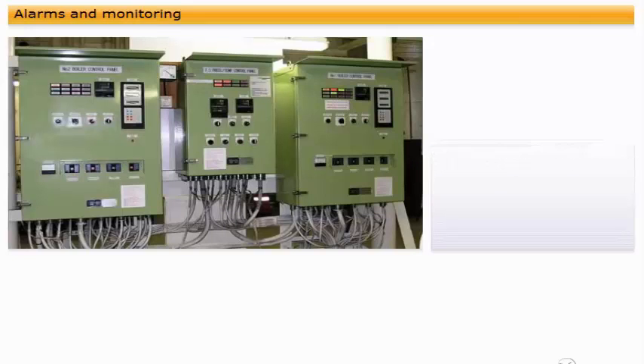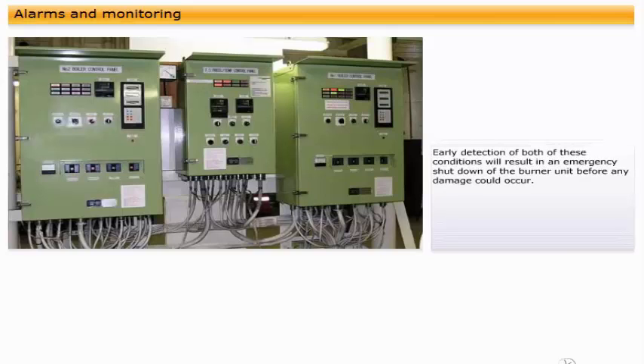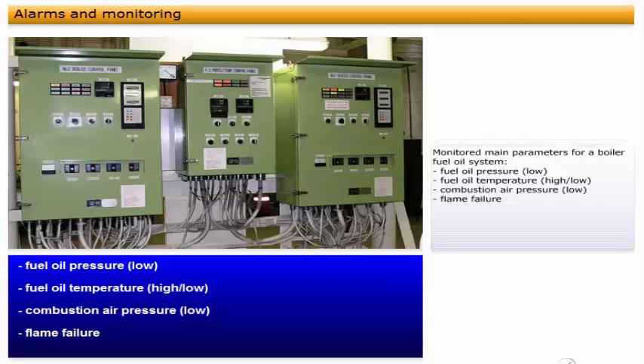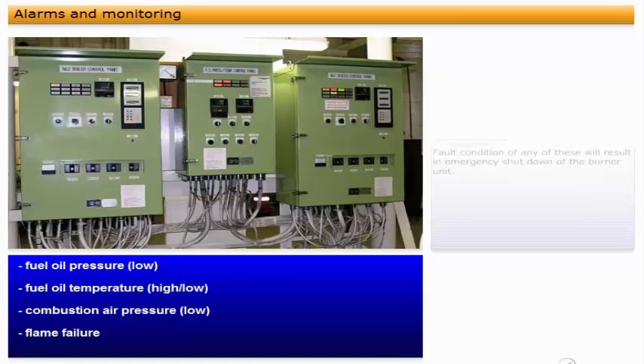High steam pressure can lead to rupture of the boiler. Early detection of both of these conditions will result in an emergency shutdown of the burner unit before any damage could occur. The list shows the main parameters that are monitored for a boiler fuel oil system. Fault condition of any of these will result in emergency shutdown of the burner unit.